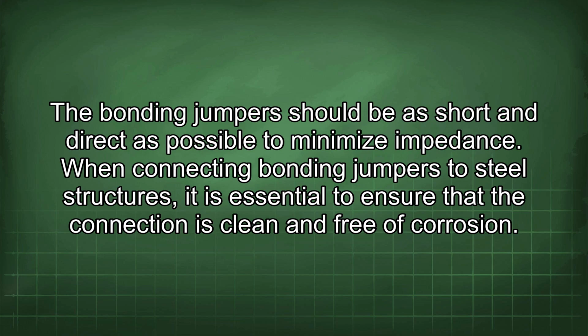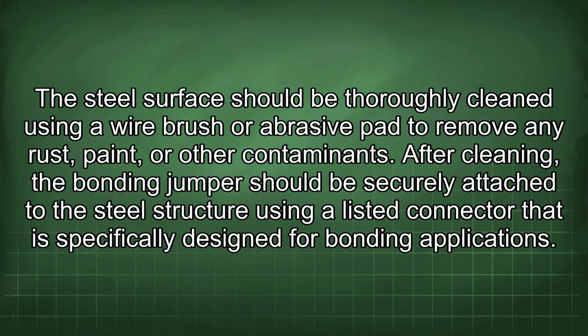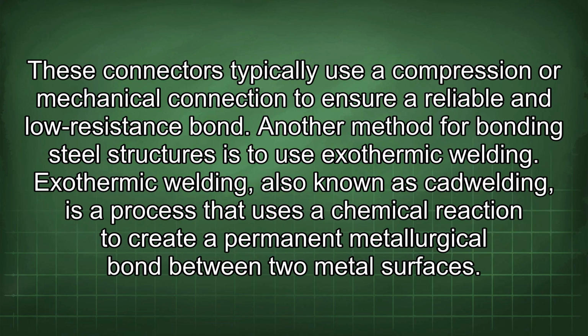When connecting bonding jumpers to steel structures, it is essential to ensure that the connection is clean and free of corrosion. The steel surface should be thoroughly cleaned using a wire brush or abrasive pad to remove any rust, paint, or other contaminant. After cleaning, the bonding jumper should be securely attached to the steel structure using a listed connector that is specifically designed for bonding applications. These connectors typically use a compression or mechanical connection to ensure a reliable and low resistance bond.